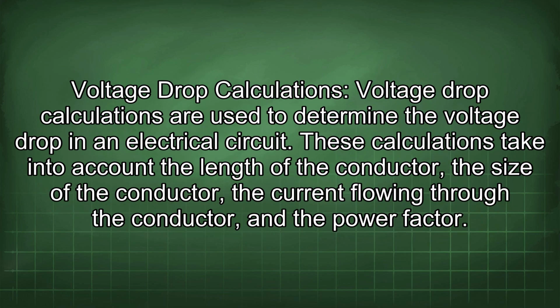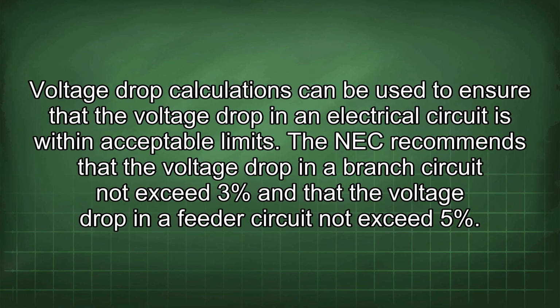Voltage drop calculations. Voltage drop calculations are used to determine the voltage drop in an electrical circuit. These calculations take into account the length of the conductor, the size of the conductor, the current flowing through the conductor, and the power factor. Voltage drop calculations can be used to ensure that the voltage drop in an electrical circuit is within acceptable limits. The NEC recommends that the voltage drop in a branch circuit not exceed 3% and that the voltage drop in a feeder circuit not exceed 5%.